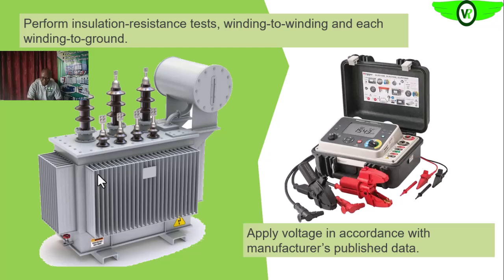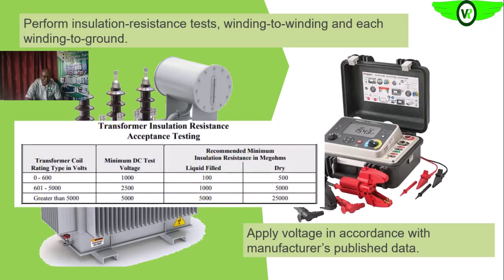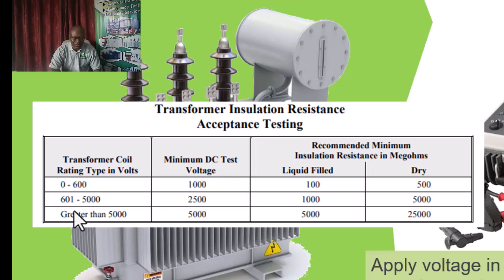So we apply voltage according to what the manufacturer recommended, or what is specified in our facility. That is what we are going to be using. But in the absence of that, we can use this as a guide. These are some of the ratings in volts of the transformer: between 0 and 600, 600 and 5000, then greater than 5000. So the voltage that we have to inject or apply between the areas that we are testing the insulation, if it is between winding and ground, we place one probe on any of the windings since it is connected inside, and then the other probe to ground. If it is in the first range, we apply 1000 volts. If it is in this range, we apply 2500. If it is greater than 5000, we apply 5000 volts.